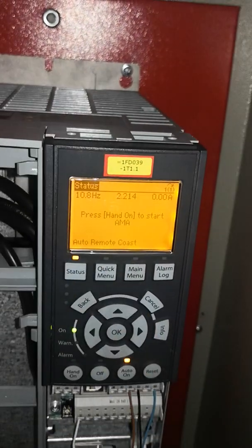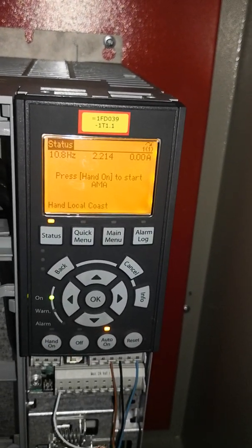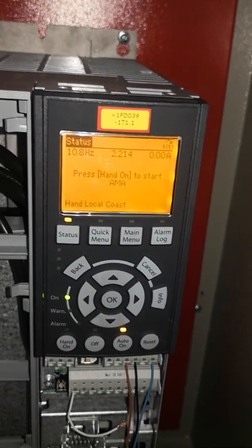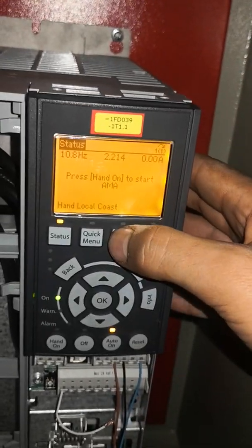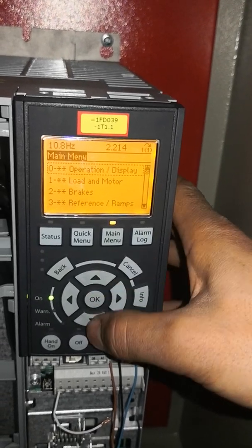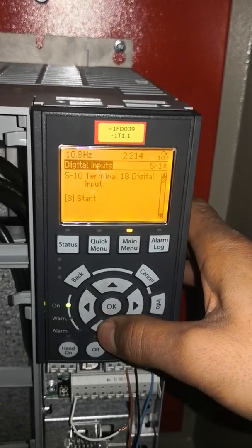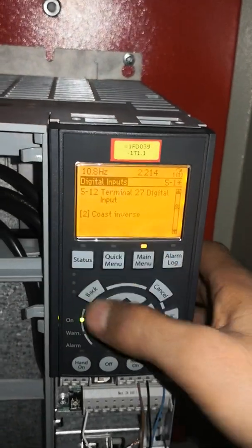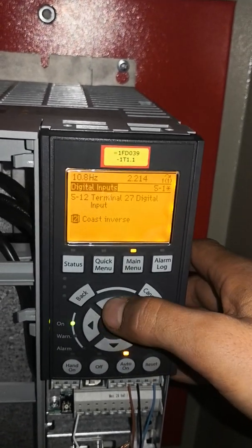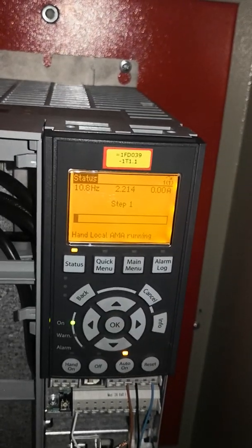We should enable Complete AMA and press Start. It says press Hand-On to start AMA, but pressing the Hand-On button does nothing. To fix this, go to Digital Inputs and find terminal 27 — set this parameter to zero. Now the AMA process has started.